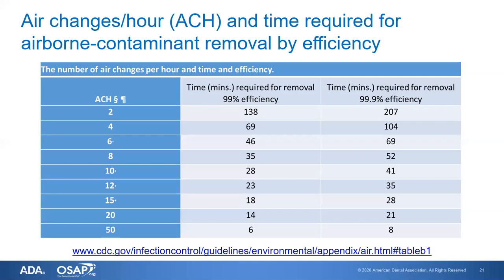A very common air exchange rate is six per hour, and that would take 46 minutes for 99% of the air to be exchanged in that room at that rate. That's not to say you necessarily have to leave a room empty for that many minutes — it's just saying that if you want to know how long it takes to completely change over the air in a room, this chart will give you that information.